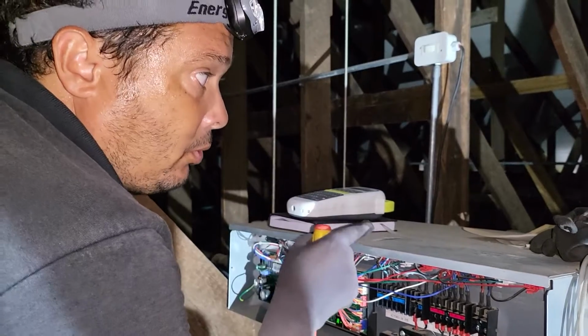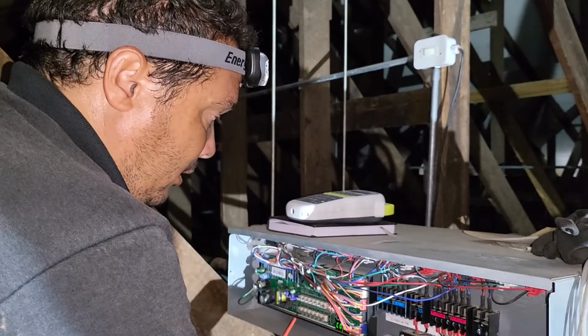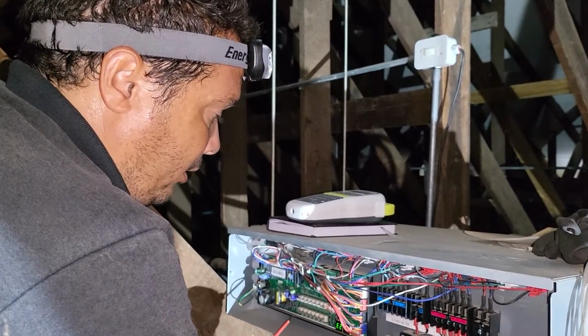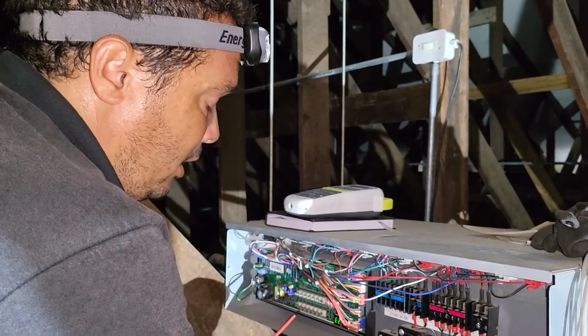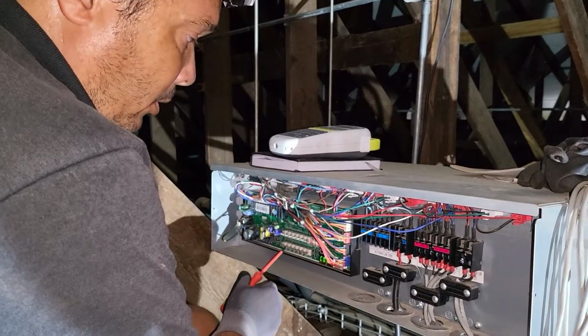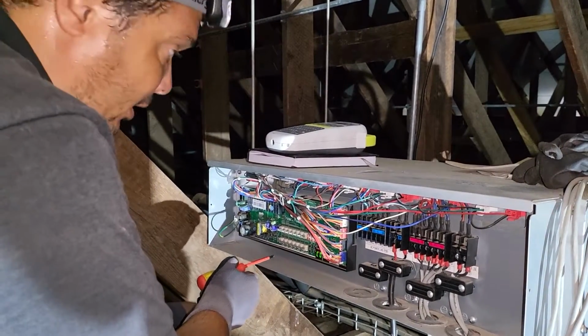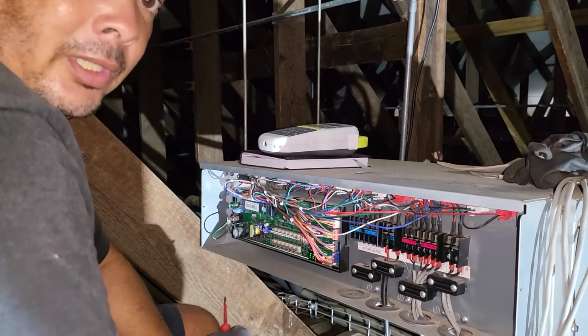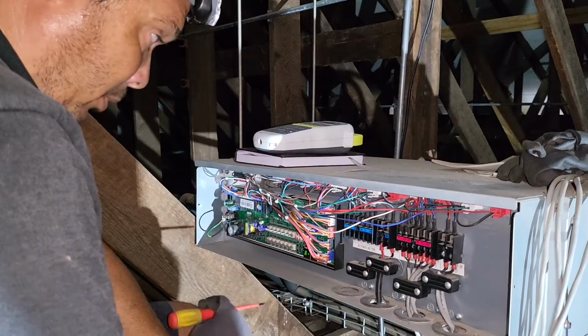The second set of piping does exactly the same thing, with 2 circuits going into one branch into one system, which means the next address in the sequence would be 11, so you'd expect to see C and D both at 11. That's exactly what we have here, and then the rest of the addressing is pretty much done properly.